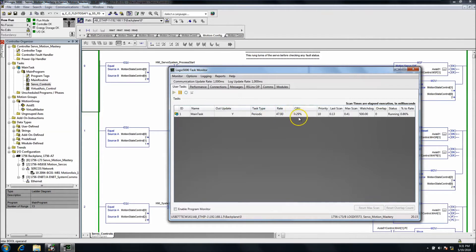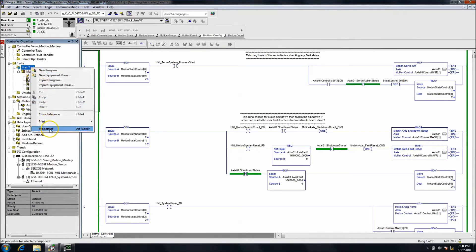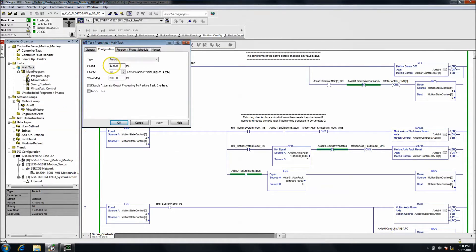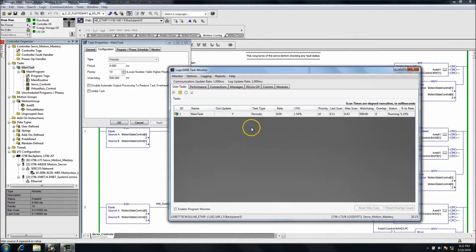You can see I'm using very, very little CPU usage on this program. It's an L73 processor, but it's using very little of it. I can change this task rate from 47 down to probably like 8 and it still wouldn't affect it — that's because I'm not using much of the program at all. It's only one task, but you did see the CPU usage go up when I did that.